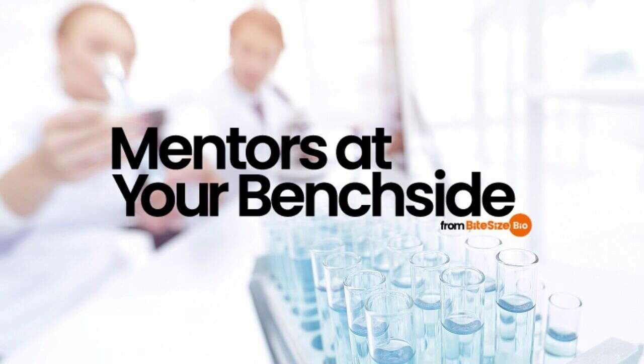Tip number 4. Use the right tubes. If for some reason your tubes break, melt, or disintegrate during centrifugation, samples will leak and throw the delicate balance off. This can mean a damaged rotor or bits of tube flying around wreaking havoc. Remember that a small mass with all that centripetal force can cause serious damage.